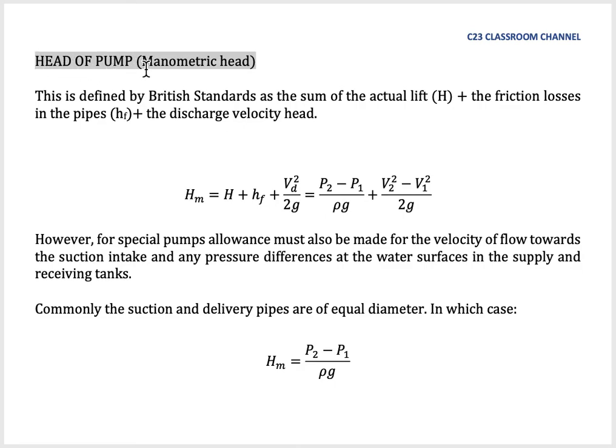It's also called manometric head. This is defined by British standard as the sum of the actual lift head H, plus the friction losses in the pipe hf, plus the discharge velocity head. It can be written as H_m, the manometric head, is the total head of actual head plus the friction loss in pipe plus the discharge velocity head. It also can be written as H plus hf plus Vd squared over 2g, which equals P2 minus P1 over rho g, plus V2 squared minus V1 squared over 2g. We could get this from the Bernoulli equation.